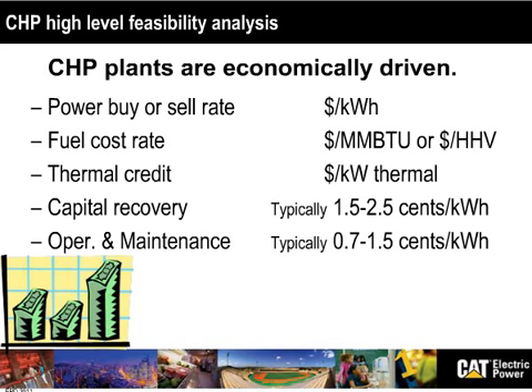Thanks. Typically, a steam heat recovery costs a bit more to operate than hot water. Steam boilers, they need special water to go into. You need the water treatment and so on. So that's probably in the high end of the 1.5s. And hot water is more simple.